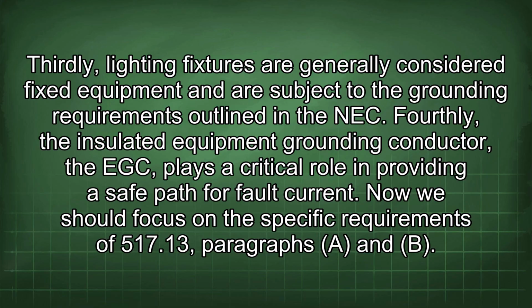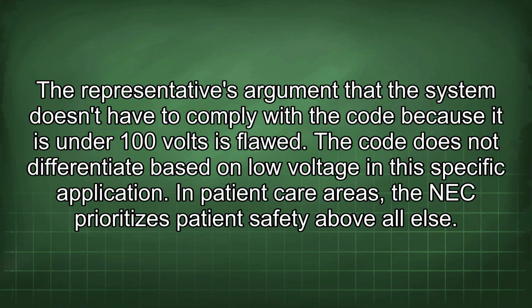Fourthly, the insulated equipment grounding conductor, the IG, plays a critical role in providing a safe path for fault current. Now we should focus on the specific requirements of 517.13 paragraphs A and B. The representative's argument that the system doesn't have to comply with the code because it is under 100 volts is flawed. The code does not differentiate based on low voltage in this specific application. In patient care areas, the NEC prioritizes patient safety above all else.